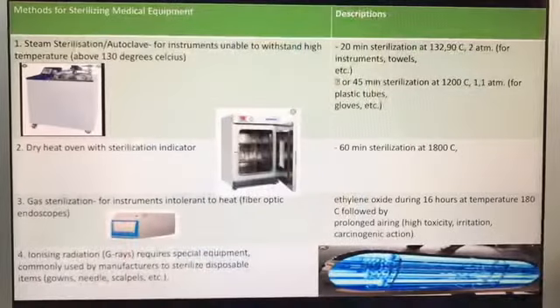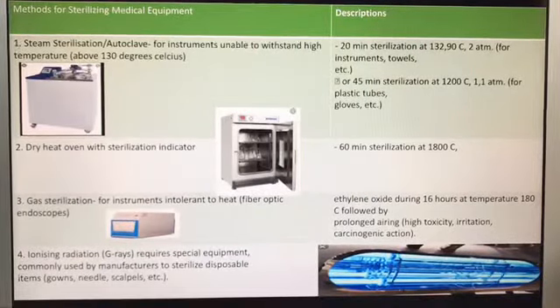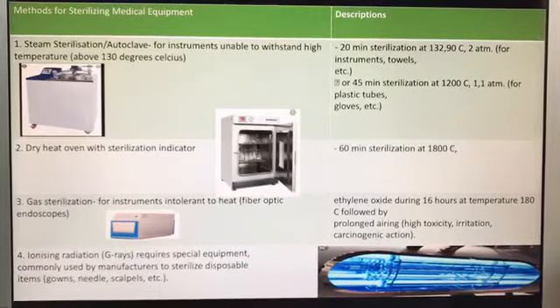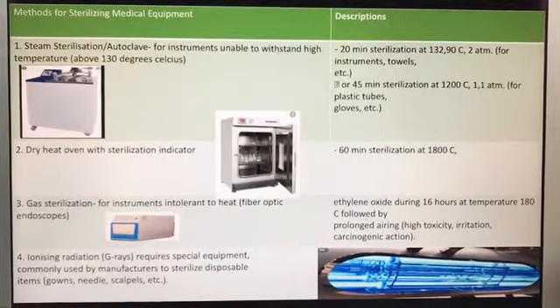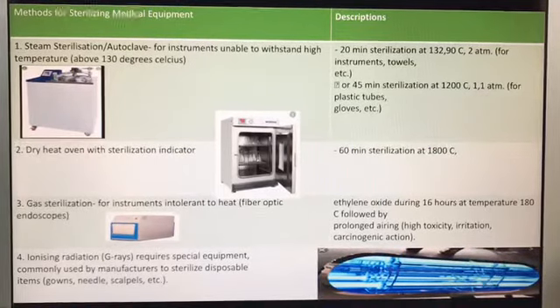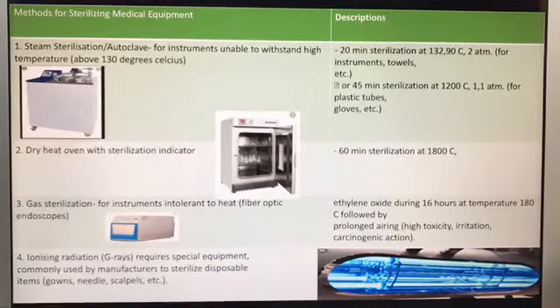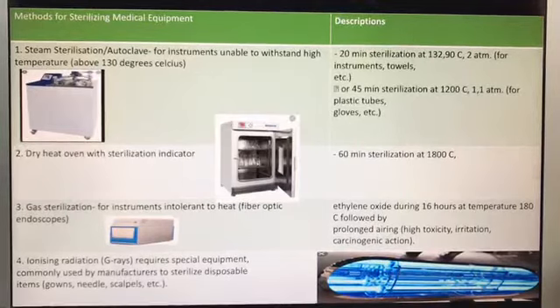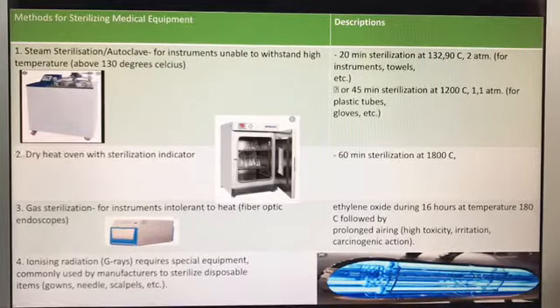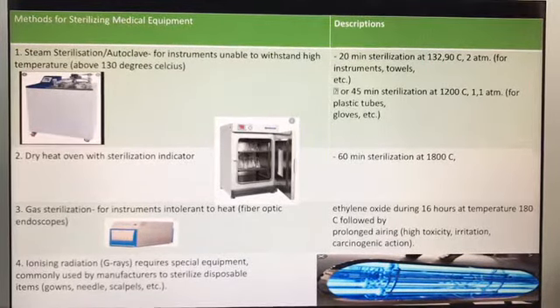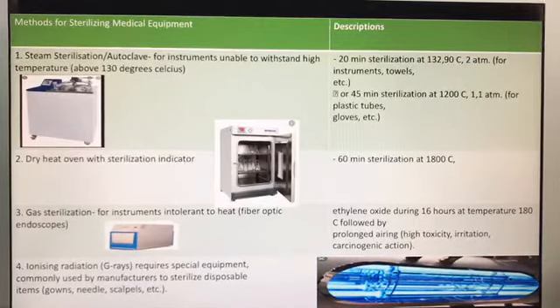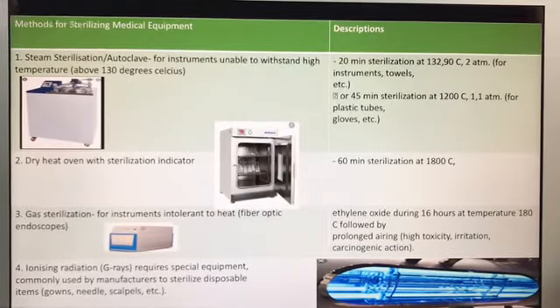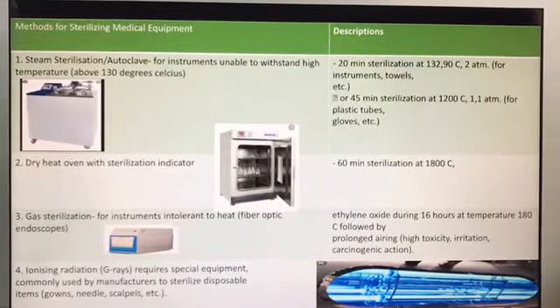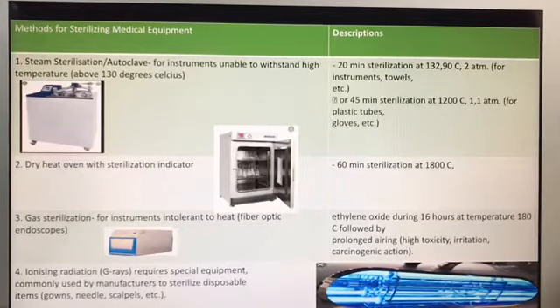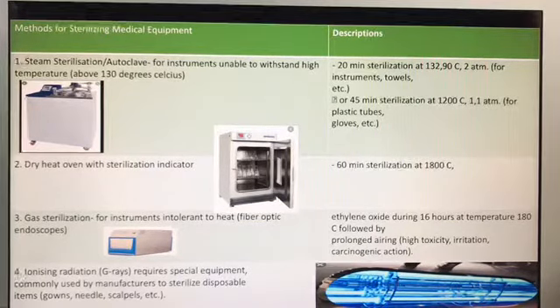Lastly, we have ionizing radiation or gamma rays, which requires special equipment and is commonly used by manufacturers to sterilize disposable items like gowns, needles, scalpels, etc. In the context of sterilization, ionizing radiation is a type of short-wavelength, high-intensity, low-temperature radiation that is used to destroy all microorganisms during sterilization. The forms of ionizing radiation used for sterilization are known as gamma irradiation, electron irradiation, and X-ray irradiation.